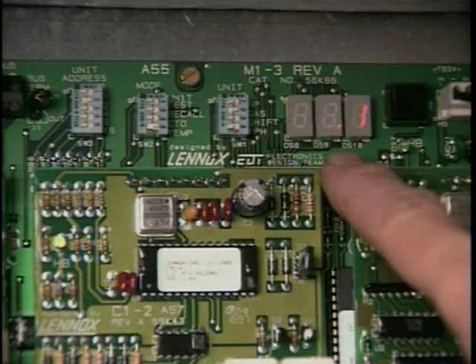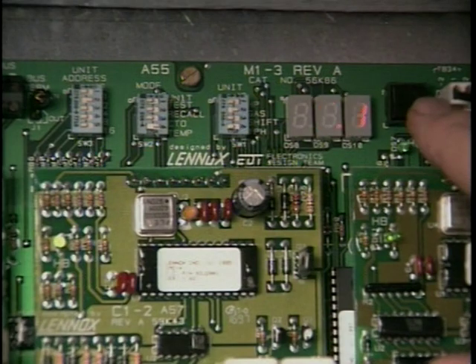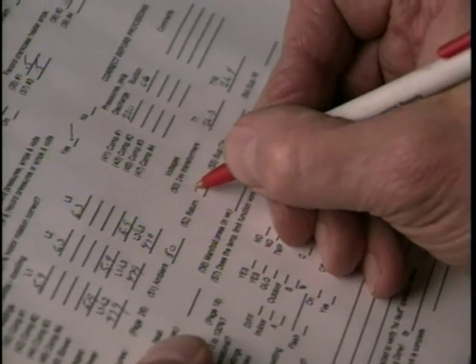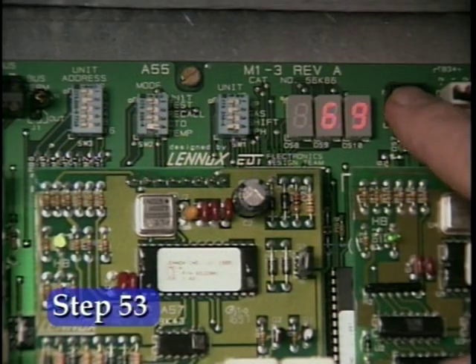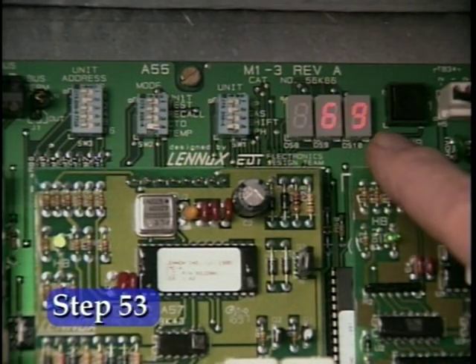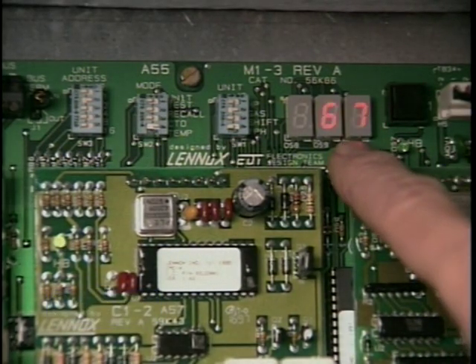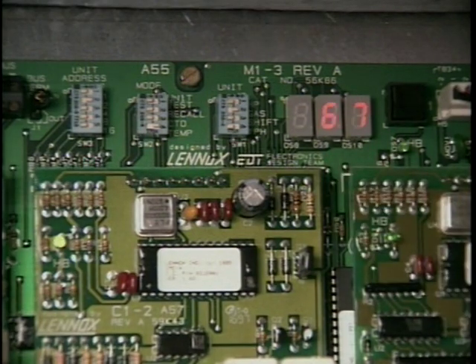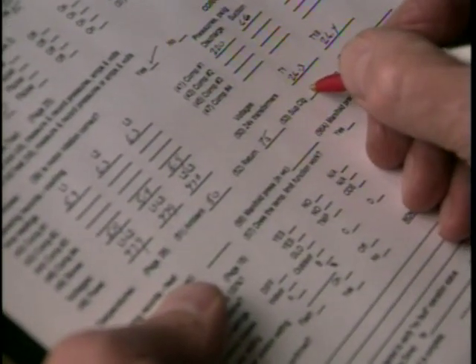The LED readout will alternate between point 1 and the return air temperature. Record the return air temperature in space 52. Press the display push button once to advance to point 2. The LED readout will alternate between point 2 and the supply air temperature.